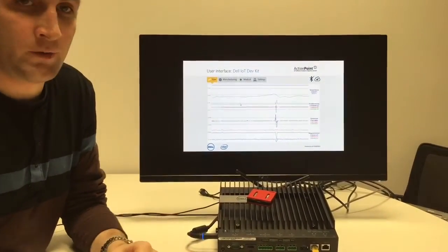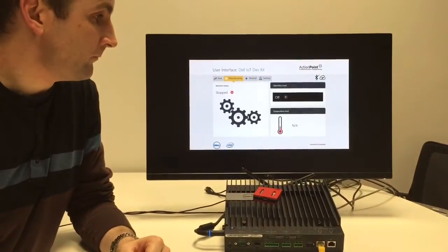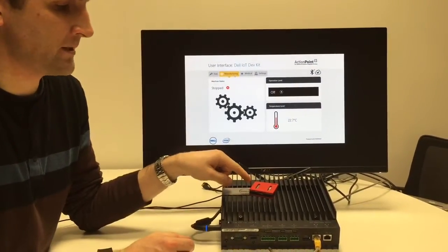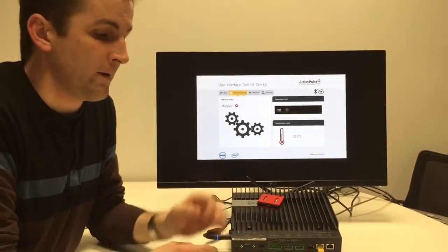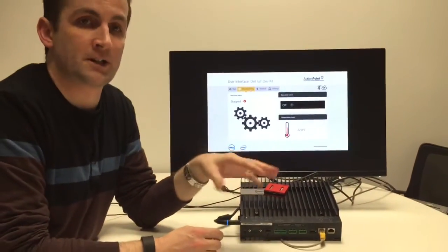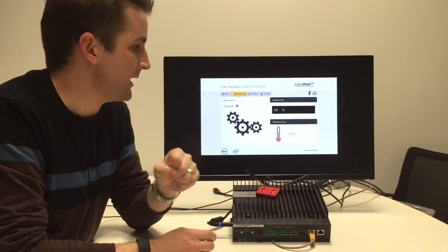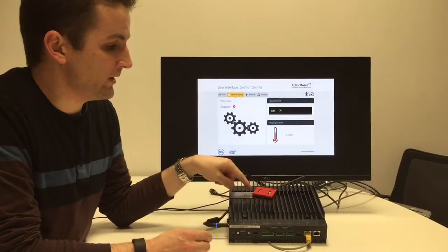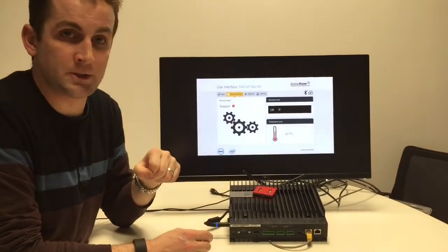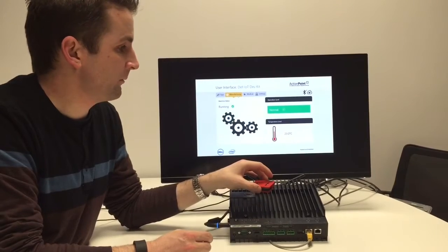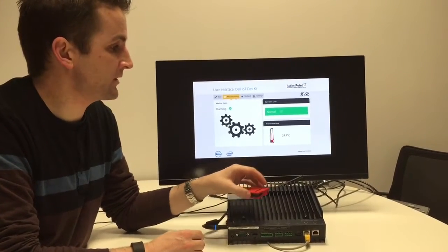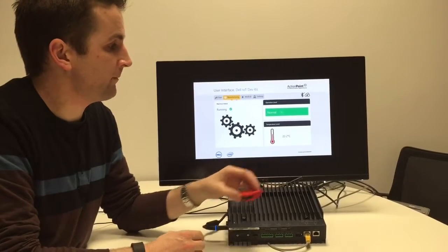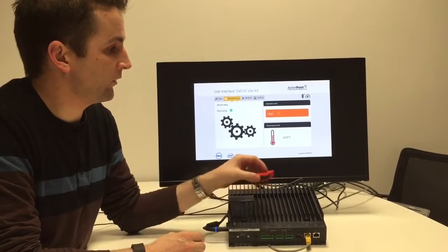So imagine, if you will, we're in a manufacturing space. You might use accelerometers like the ones in this device and put them on the side of a machine. Every machine that's running always has a vibration profile, a vibration shape. In this scenario, we know that this is not vibrating right now, so we know your machine is stopped. If there's a small bit of vibration, we know that it's running, and that's fine. Now, if the vibration starts to go a little bit out of whack, we can raise alerts. So it goes high.